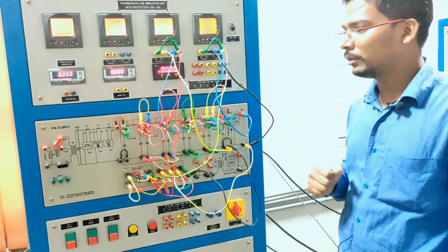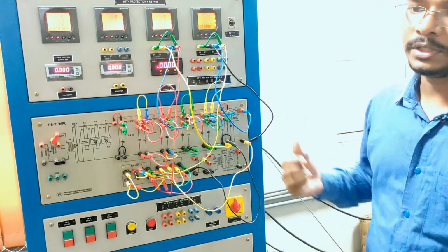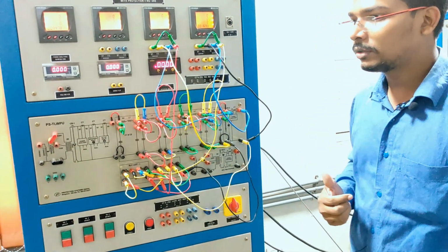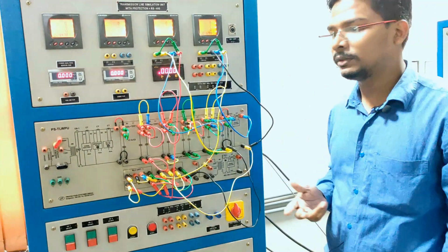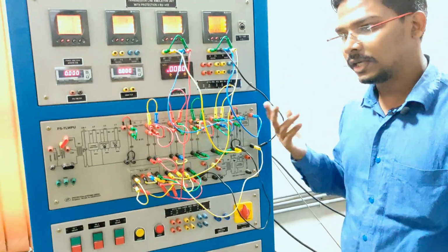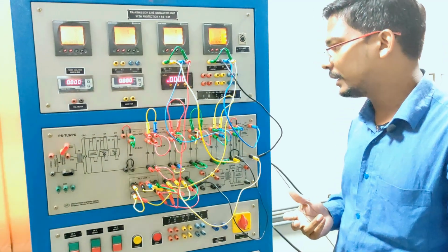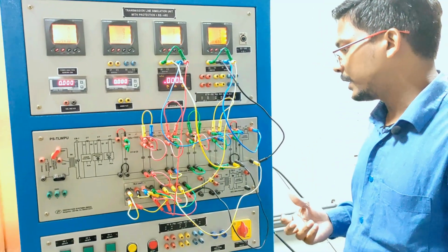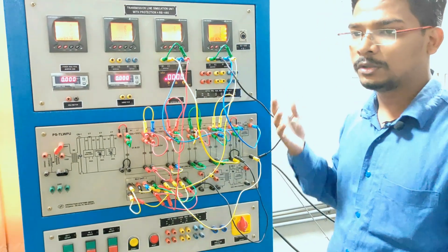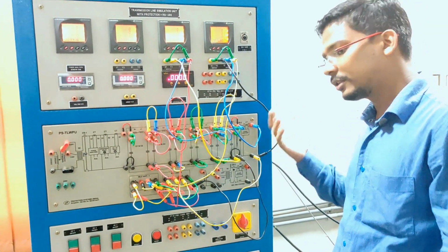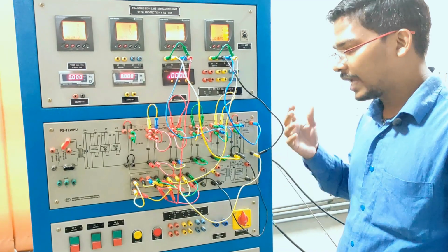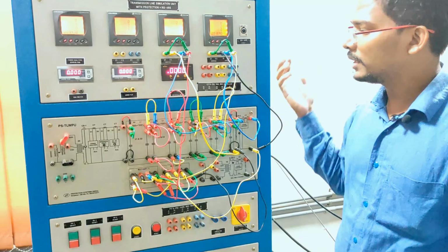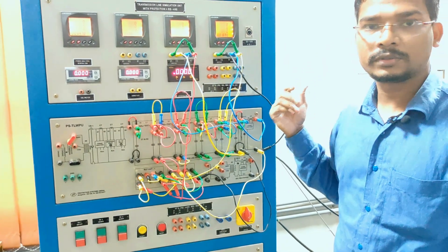And one thing also you will notice is that every transmission line has a SIL, that is the surge impedance loading. In another experiment we will find the surge impedance loading of the transmission line. By knowing it we can conclude what will happen if we apply that much load across the transmission line. At that condition there will be no requirement of a compensator, and we will get zero voltage regulation. So that is the SIL.